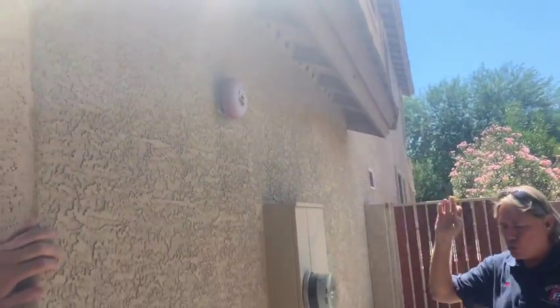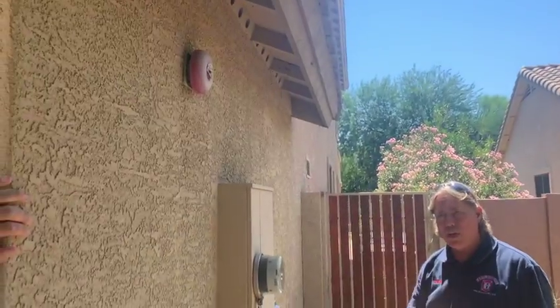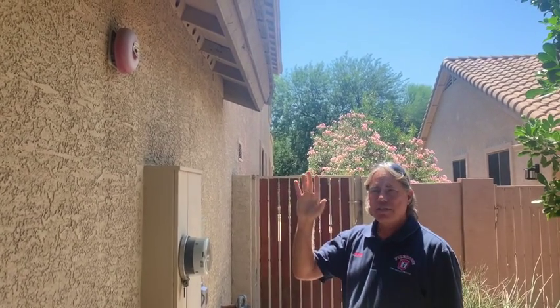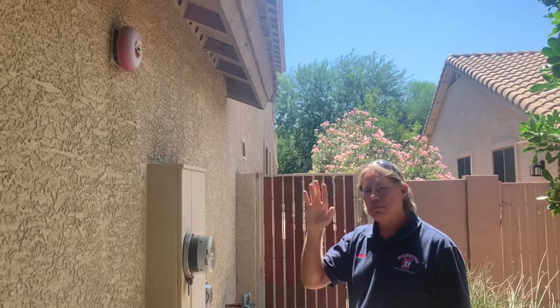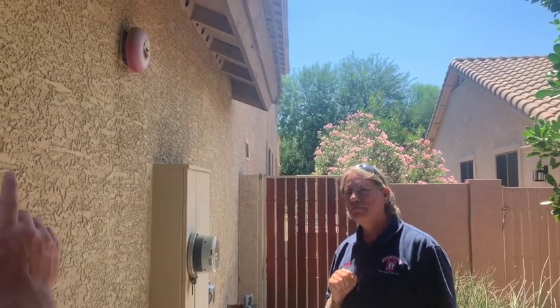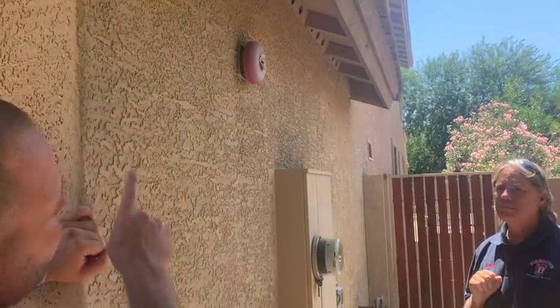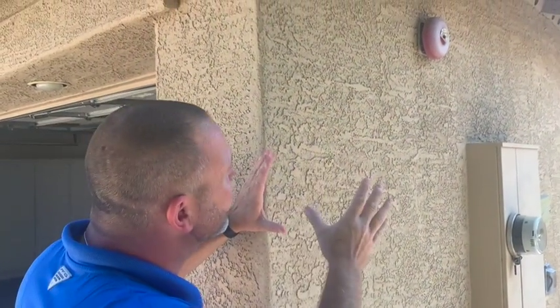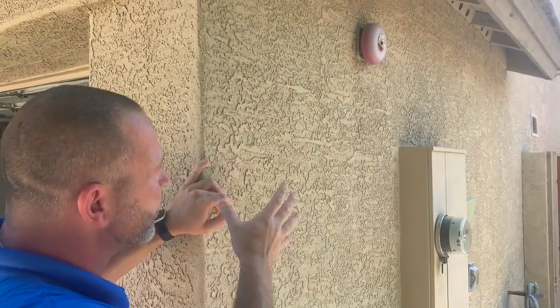That fire bell, it's crucial that that does operate when the fire sprinkler system flows. I've seen cases where that's saved people's lives. And I could go into more detail about that, but suffice to say that is very much an important part of the fire sprinkler system. It needs to ring. So what you're saying is that this bell doesn't go off if I burn Thanksgiving dinner and the smoke alarms are going off on the inside.